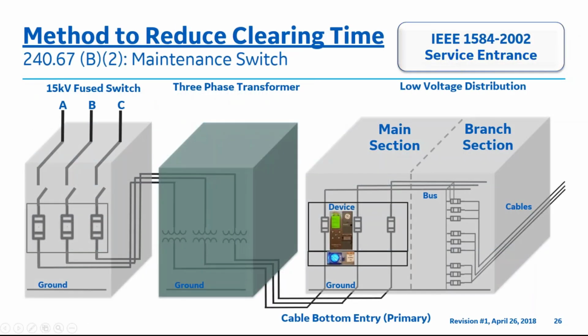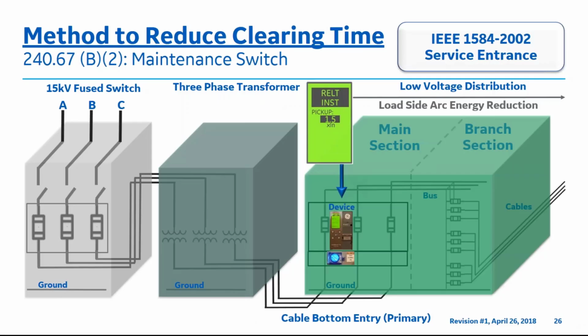The application of 240.67(B)(2), the maintenance switch: this method requires low voltage access to the load side main section distribution, which are bottom or top entry, noted here, of the equipment that can clear the arcing current requirement within 0.07 seconds or less for fuses. If an arcing current event occurs at this location, with the red X drawn here, the electronic device will provide load side arc energy reduction for the power distribution section in this application.